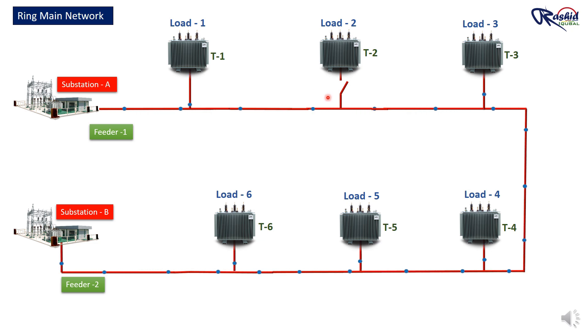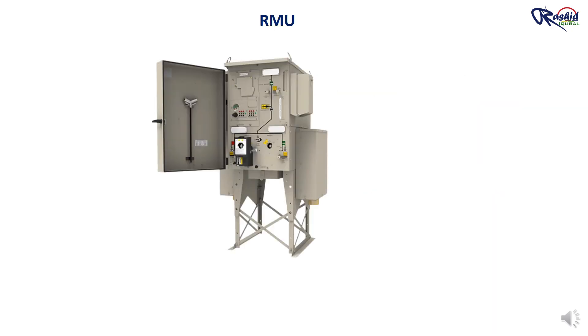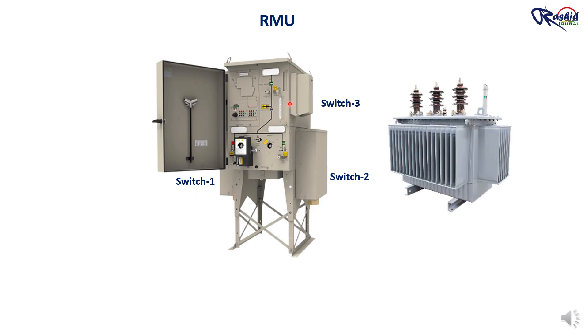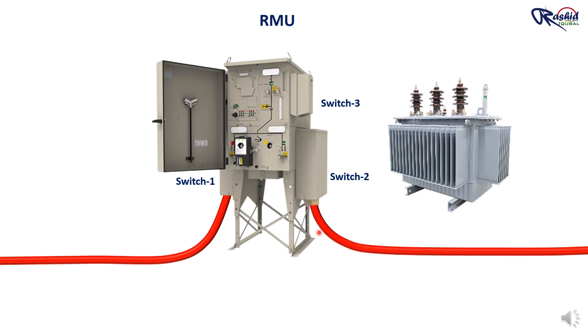Now, instead of installing these three switches separately, we can combine them into one switchgear called Ring Main Unit. In this setup, I have combined different switches into one unit — Switch 1, Switch 2, and a circuit breaker, all in one, which we call RMU, that is Ring Main Unit. Switch 1 brings in the power, Switch 2 passes power to the next RMU or feeder, and the third switch is the circuit breaker that connects to and protects the transformer.